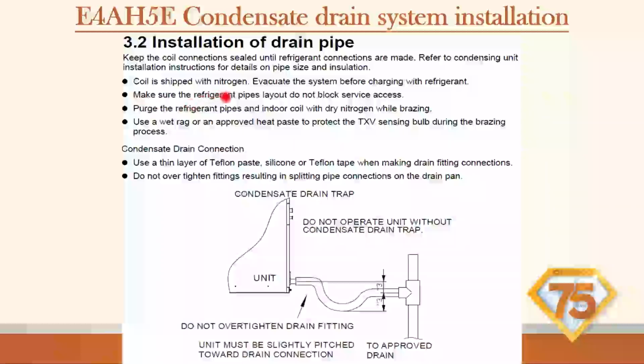Make sure the refrigerant pipe layout does not block the service access. So make sure we can still remove those doors. You're going to purge the refrigerant pipes and indoor coil with dry nitrogen. That's always a must. I can't stress that enough while brazing. And I'll go over why that is even more critical in this situation with these units.